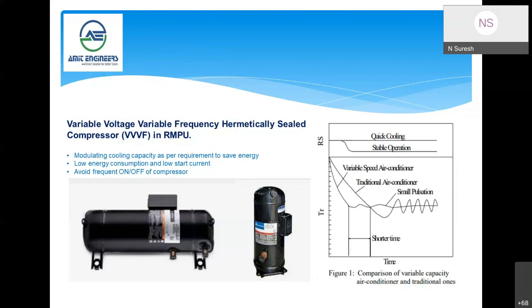While on off, for any compressor, during the on stage the initial starting current will be very high. In this case, the starting current will increase very gradually, since it is running through the drive. The drive itself starts from the lower frequency and gradually goes to higher frequency. The compressor can run continuously without on and off when the temperature is reached. When there is no cooling required, we can run at a very low frequency, so that the other compressor will be switched off. This will definitely help in railway, as the starting current will be very, very minimal.